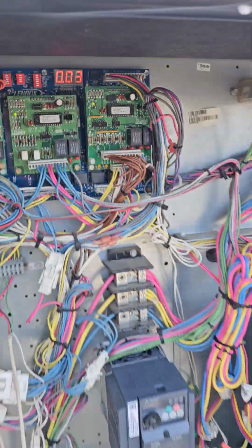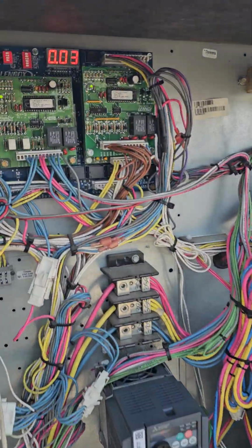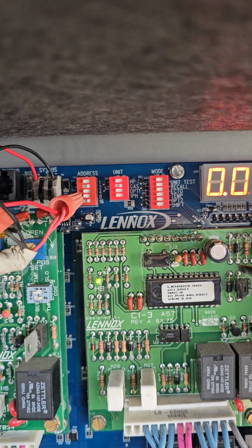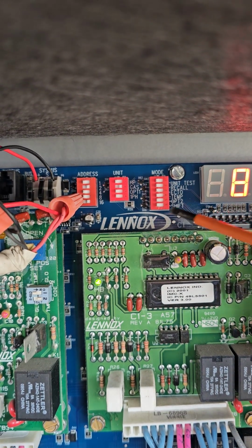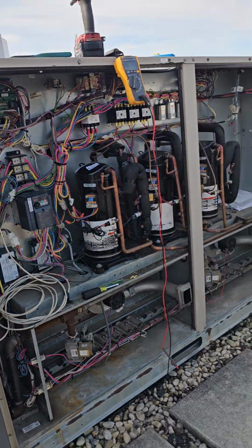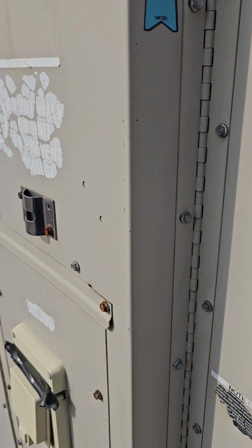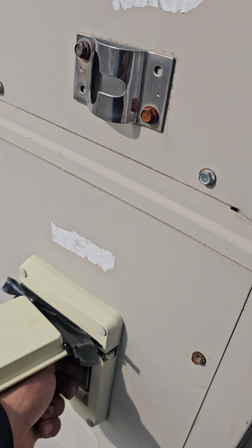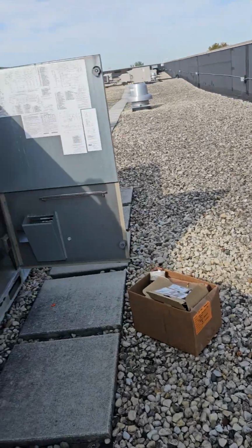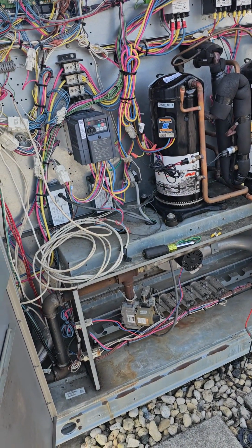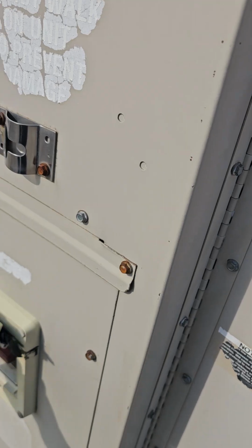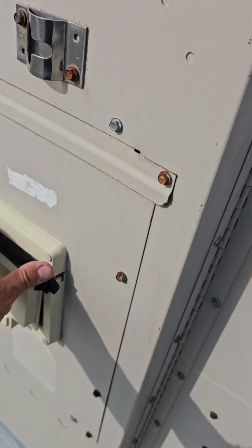Okay? And then as a rule of thumb, once you're done with that, I always come back. Once you're done setting all your parameters, click that electronic control dip switch back over to the left. And then as a rule of thumb, guys, I know a lot of guys forget about it, but better safe than sorry. Shut the power off. Wait until the VFD has drained all energy out. You can see it blinking, and there we go. So the capacitors have officially drained all the stored energy in there.